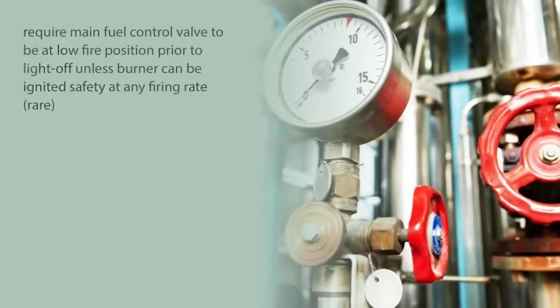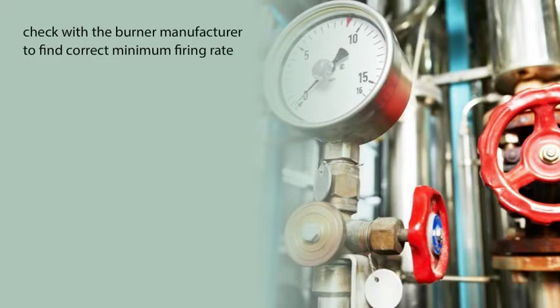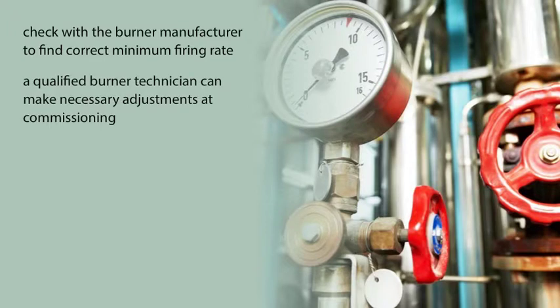Most systems also require the main fuel control valve to be at a low fire position prior to light off, unless the burner can be ignited safely at any firing rate, which is rare. This usually means that the fuel flow control valve is proven to be somewhere between 15 and 25% of high fire capacity. You'll have to check with a burner manufacturer to find the correct minimum firing rate for your particular equipment so that a qualified burner technician can make the necessary adjustments at commissioning.